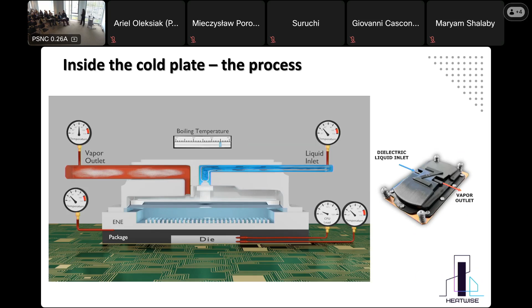Each cold plate has its own individual mechanism providing the exact amount of liquid required. You see this valve? When the liquid level lowers because of the boiling process, more liquid enters, so each component receives exactly what it needs. The pool of liquid is there all the time, preventing it from warming up, so cooling is done instantly. The minute it starts to boil, more liquid enters, keeping it cold at all times.